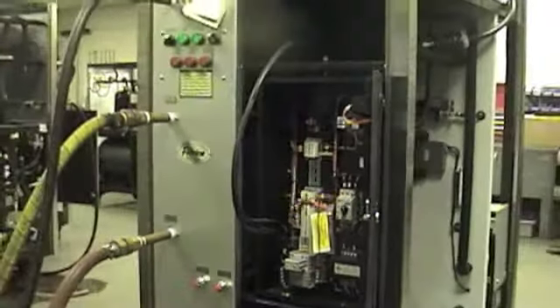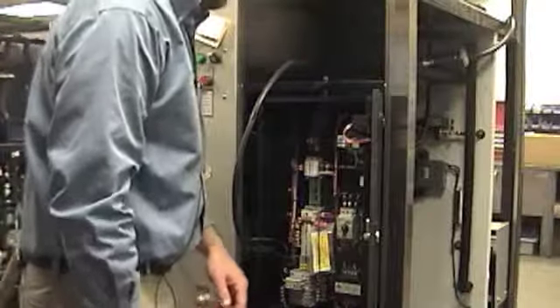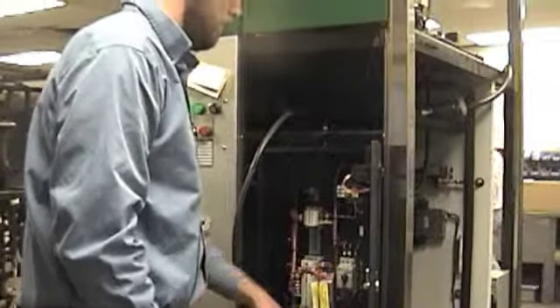We'll put on our main power. Just bump it, test the rotation. And it was corrected, so it's rotating the correct way for the arrow on the pump. So now we're ready to move on and really get the air out of the system and run the pump for a while.